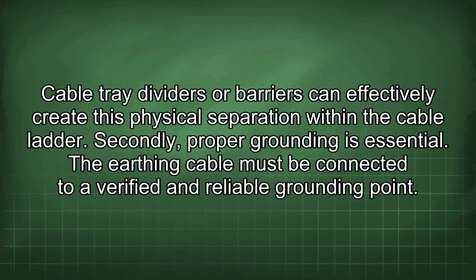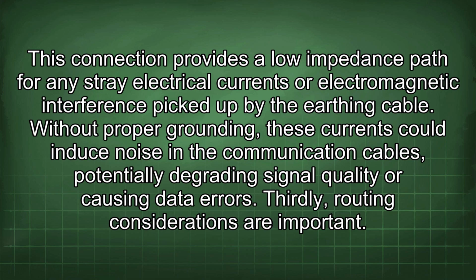Secondly, proper grounding is essential. The earthing cable must be connected to a verified and reliable grounding point. This connection provides a low impedance path for any stray electrical currents or electromagnetic interference picked up by the earthing cable. Without proper grounding, these currents could induce noise in the communication cables, potentially degrading signal quality or causing data errors.